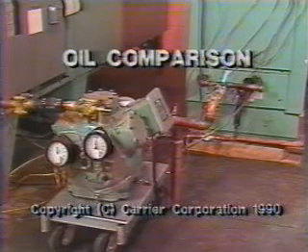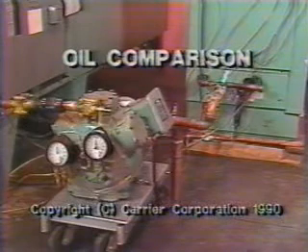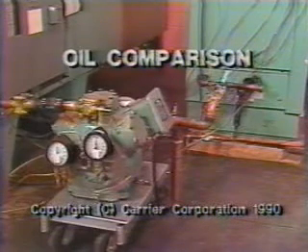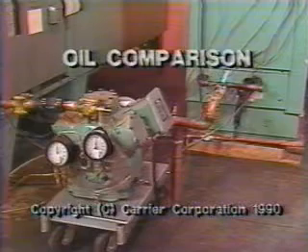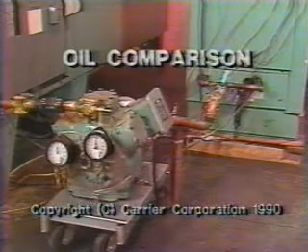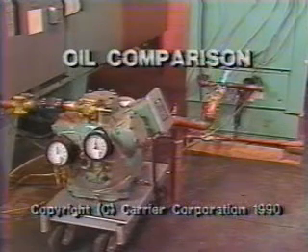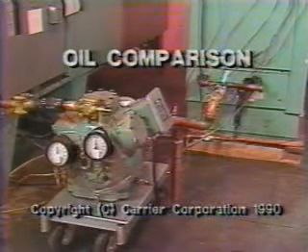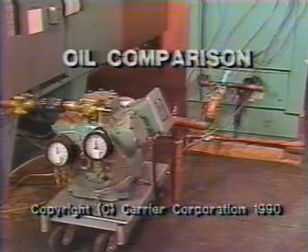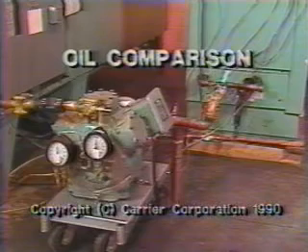Recent field returns of semi-hermetic compressors 06E and 06D have shown a type of distress in the running gear that's typical of a lightly loaded compressor with an absence of lubrication. We successfully replicated this failure in the laboratory by running the compressor with the suction service valve closed. In this video, we'll show you the difference between Zerol and 3G oils and their characteristics under this type of operating condition.